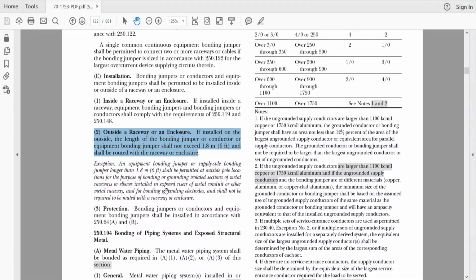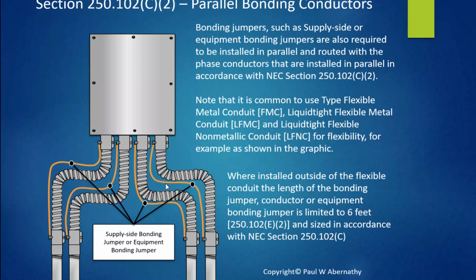Okay. Now it also gives you an exception. It talks about supply side bonding jumpers longer than 6 feet shall be permitted at outside pole locations and whatnot. So that's an exception to the general rule. So what I just want to do is to illustrate my little octopus here, because it's kind of using this. I could switch the concept here and say that this had service conductors in it, and you're running this supply side bonding jumper in parallel based on 250.102E2. Okay, and you're going to size it based on the service conductors that were in that raceway.